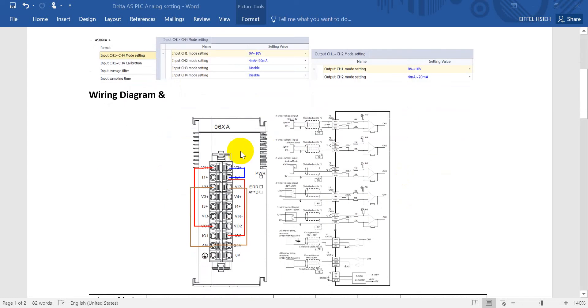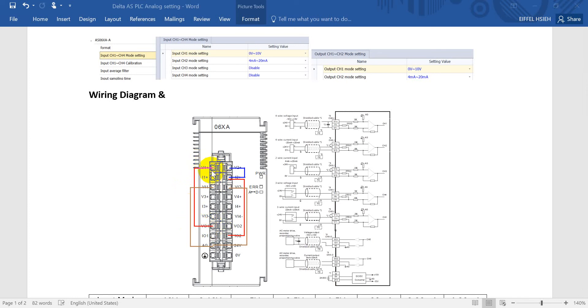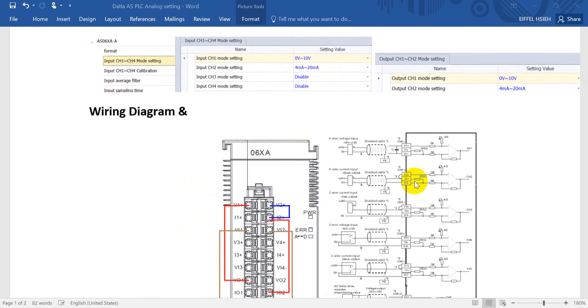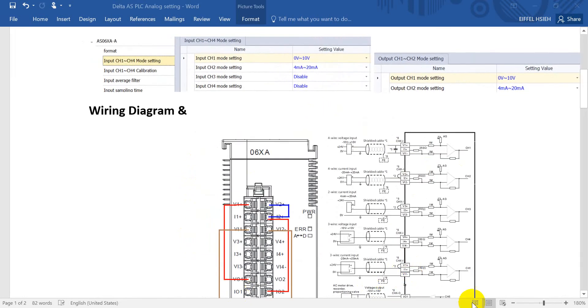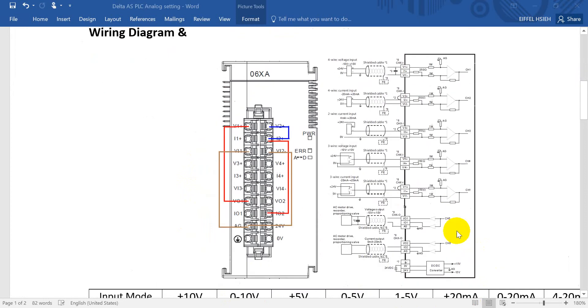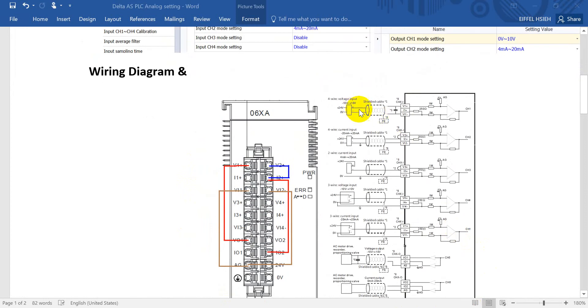You can see the wiring diagram. We will connect the voltage output from channel 1 to input channel 1, and for analog AG to minus. You can also check from here. For the plus we will connect to V1 plus, and for 0 volt we will connect to V minus.